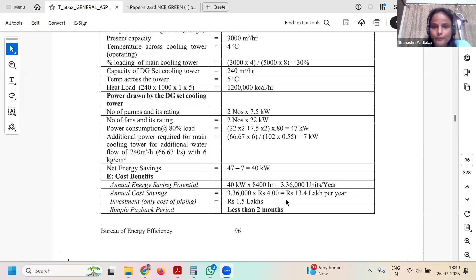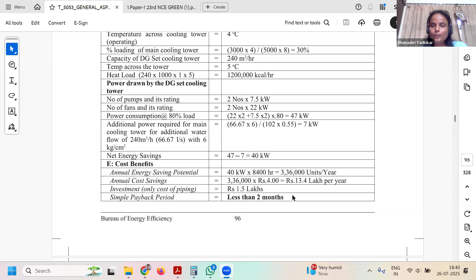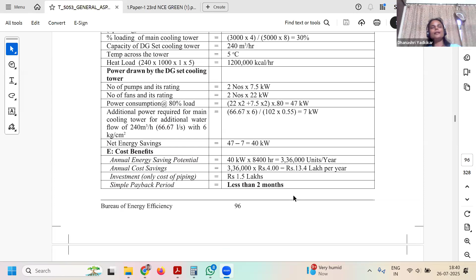The investment, only the piping is required. That means you need to just redirect the piping to the main cooling tower instead of the DG set cooling tower. So it takes 1.5 lakhs. So if you observe here, the investment is 1.5 lakhs and your annual saving is 13.4 lakhs. That means within less than 2 months you are getting your investment back. So the simple payback period is less than 2 months. You just divide 1.5 by 13.4 and you will get your answer. It's in years. You need to convert it into months. Okay. You can also mention it in years.